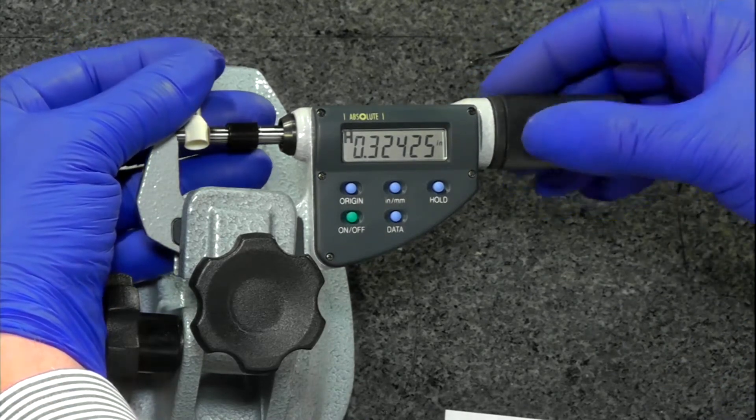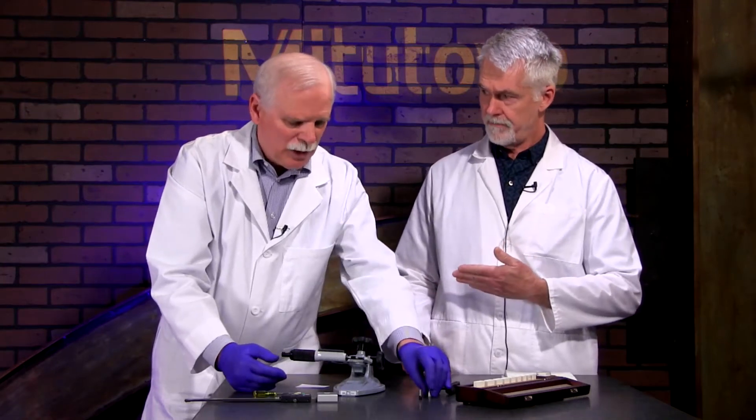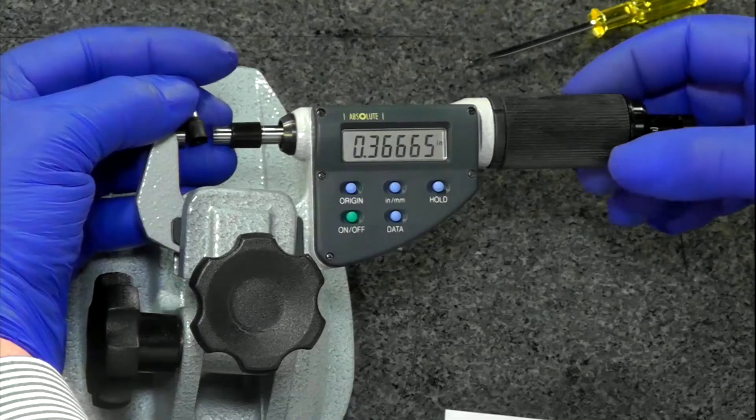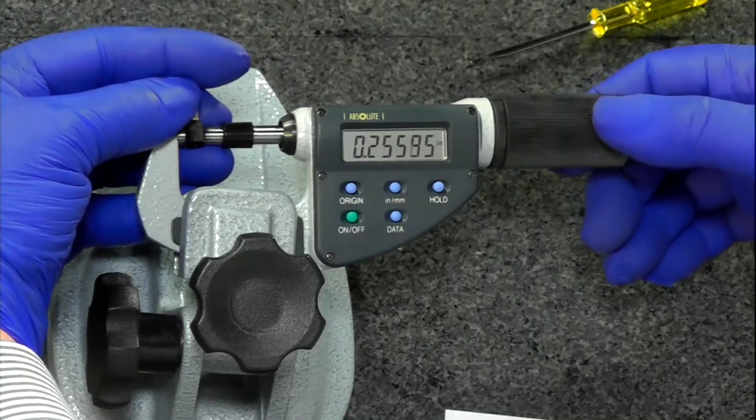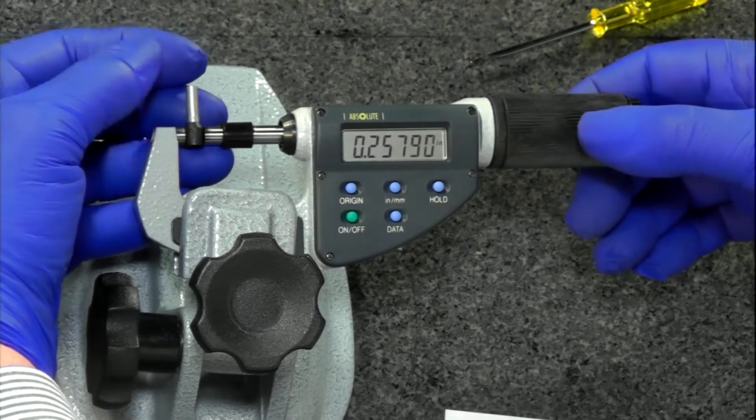Now you mentioned orientation. Is orientation of the micrometer itself matter? Yes. That is because even the components within it, when you're at these low forces are going to start showing up. And you're all about eliminating error or eliminating questions, uncertainty. Being consistent.